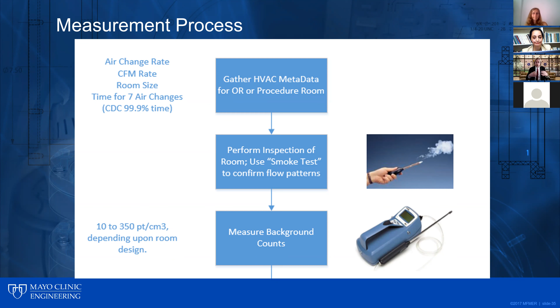So we would put a large bolus of aerosol in the room, and then we needed to measure the clearance time. The CDC standards in the United States are that the room air clearance time is the time it takes for 99.9% of the aerosols to leave the room. And it's an exponential curve, this air clearance time. So we had to characterize this curve by making measurements. We released the aerosols into the room. We had a particle counter so we could measure the exponential decay. And that's what we use to determine the air clearance time in a particular room.